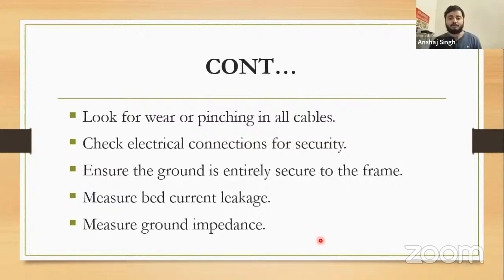Look for wear or pinching in all cables. Check electrical connections for security. Ensure the ground is entirely secure to the frame. Measure bed current leakage and measure ground impedance. So this is only for the electrical beds.